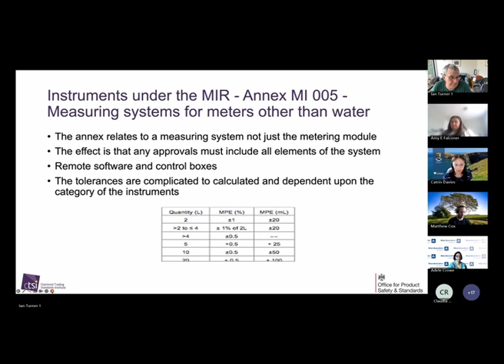So problems with meter measuring systems: clearly there's an issue with manufacturer, because quite often if you go to Tesco's or Asda or whatever, the declaration of conformity will come from Gilbarco or Tokheim or Petrotech or wherever it comes from. But quite often they will turn up on site with a declaration of conformity.